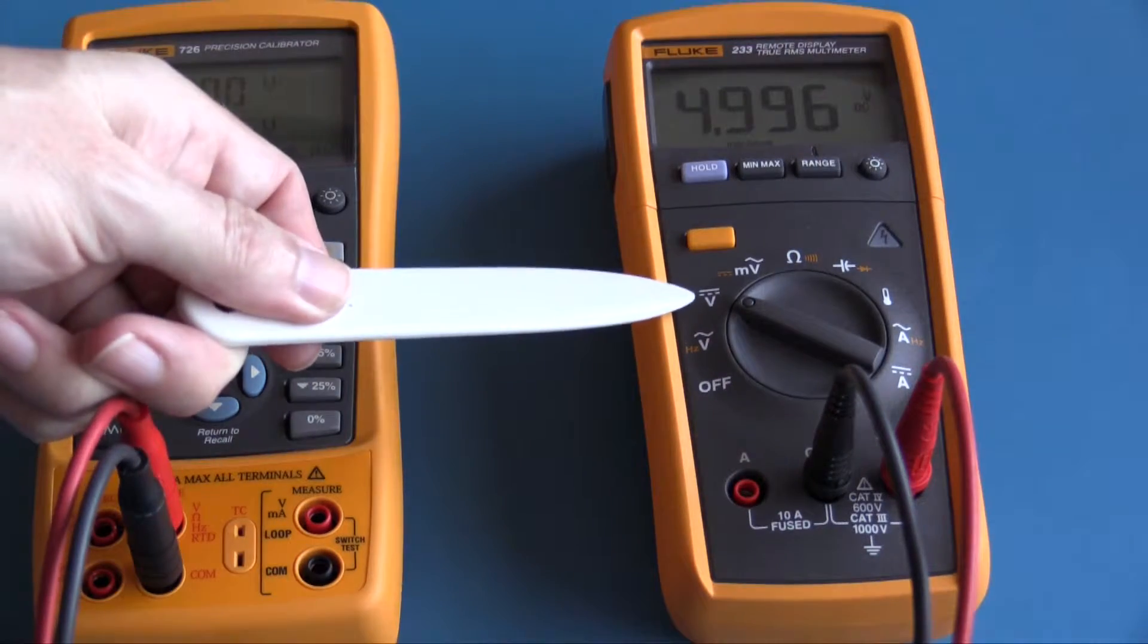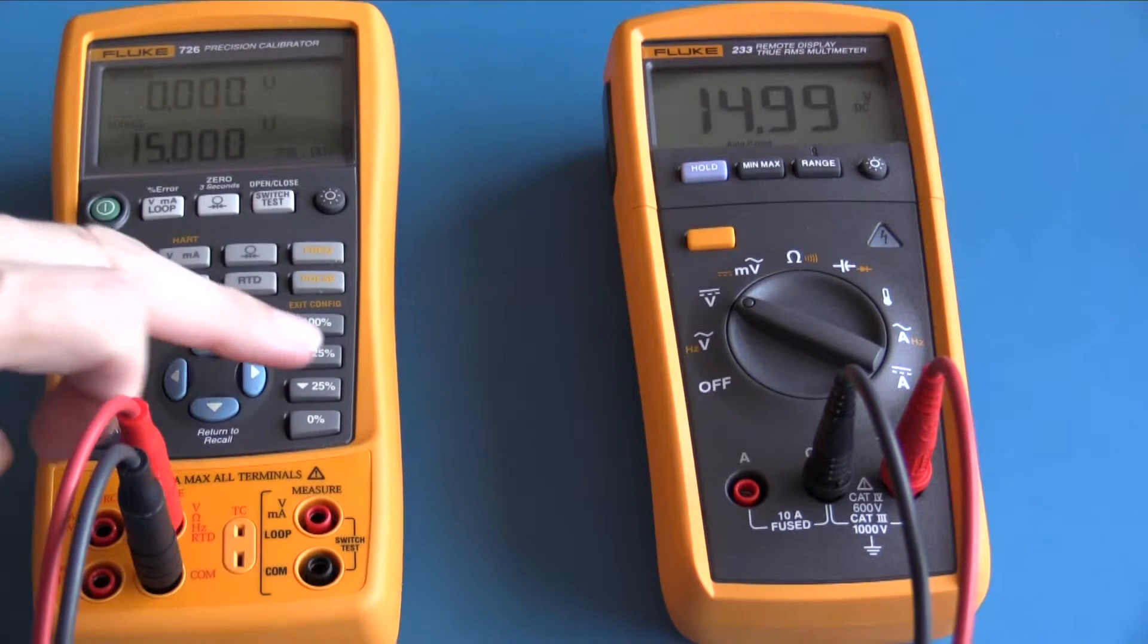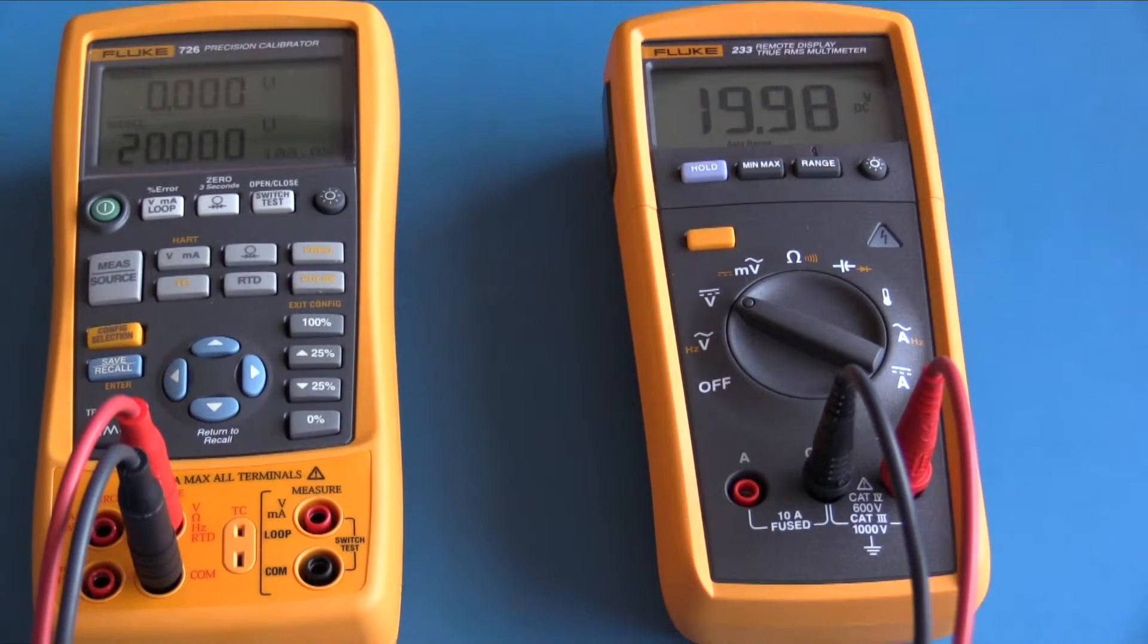I have now selected DC voltage and connected my test leads into my Fluke 726. I have the Fluke 726 set to source 5 volts. The Fluke 233 is showing 4.996 volts, so very close. Now looking at 10 volts, the Fluke is showing 9.99 volts, which is very close. 15 volts and 20 volts. The 233 is well within specification here.